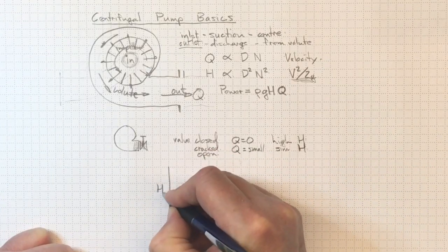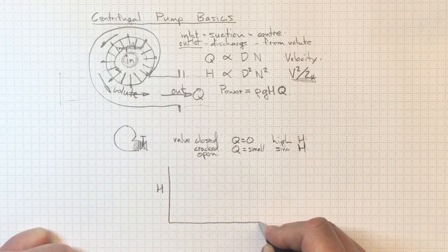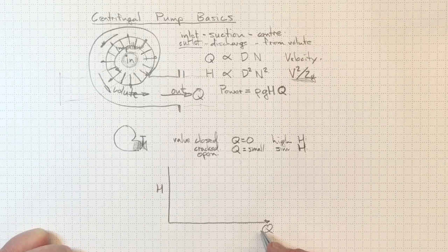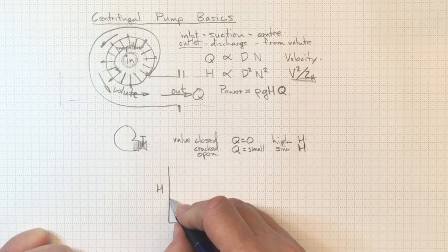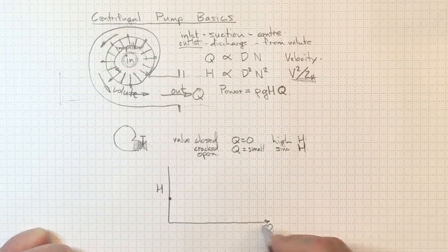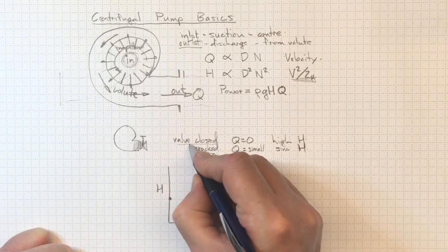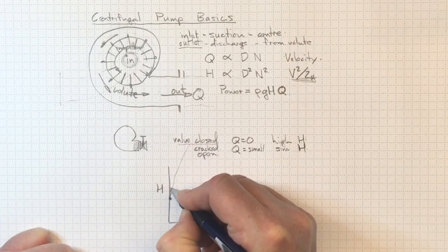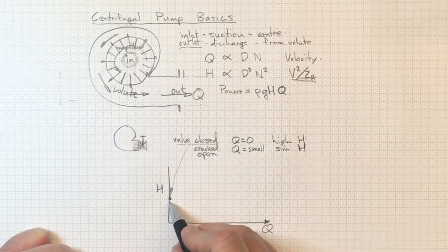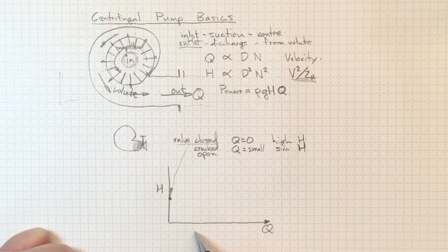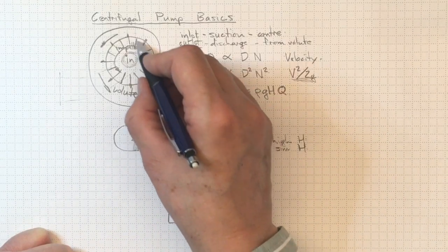If we looked at head versus flow, and this is the classic curve that we'll draw for any pump situation, then when we start here, we may have quite a high head and no flow. That's because we've got our valve closed. So that's that location there. And as we open the valve a little bit, we will get some flow going out. So we'll move up along the Q axis.